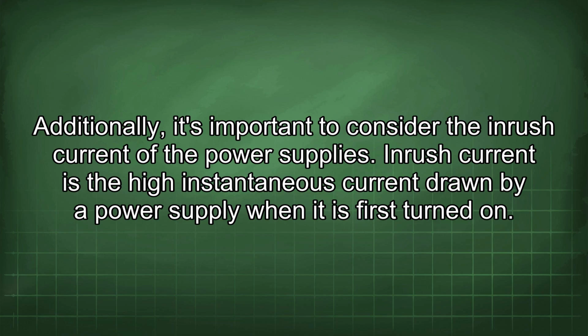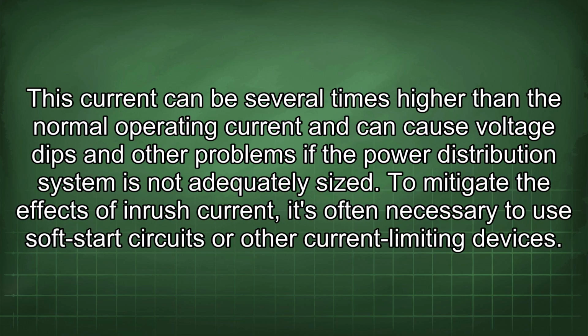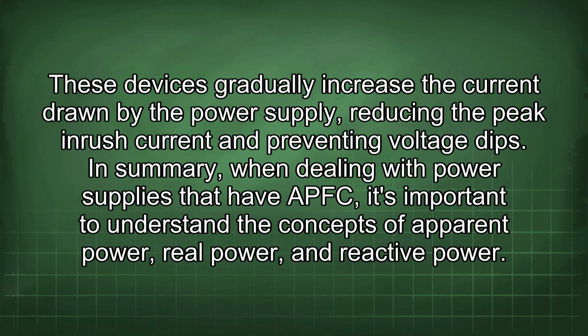Inrush current is the high, instantaneous current drawn by a power supply when it is first turned on. This current can be several times higher than the normal operating current and can cause voltage dips and other problems if the power distribution system is not adequately sized. To mitigate the effects of inrush current, it's often necessary to use soft-start circuits or other current-limiting devices. These devices gradually increase the current drawn by the power supply, reducing the peak inrush current and preventing voltage dips.